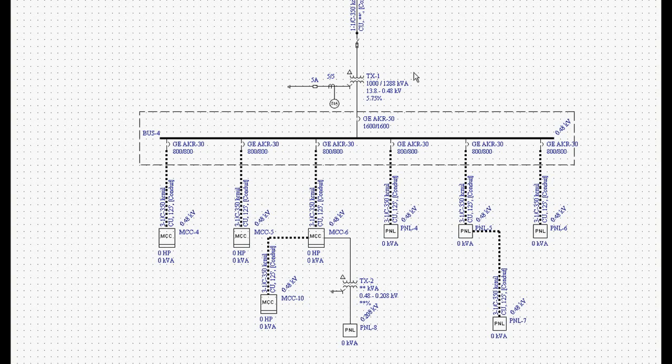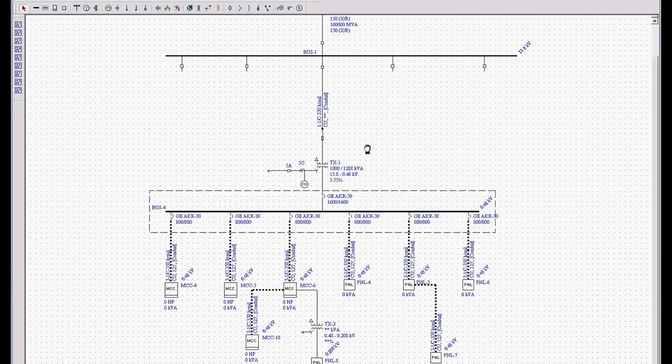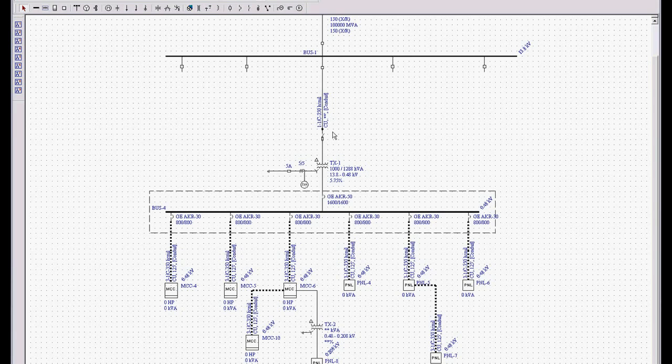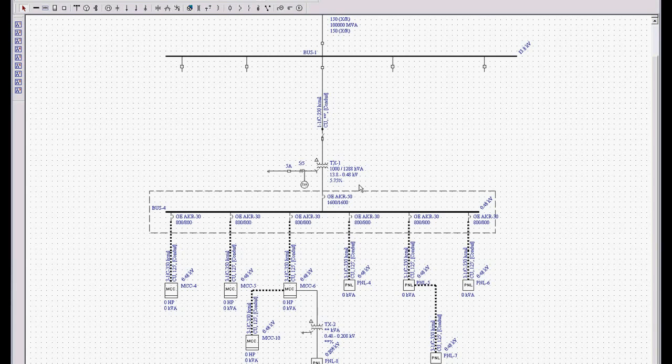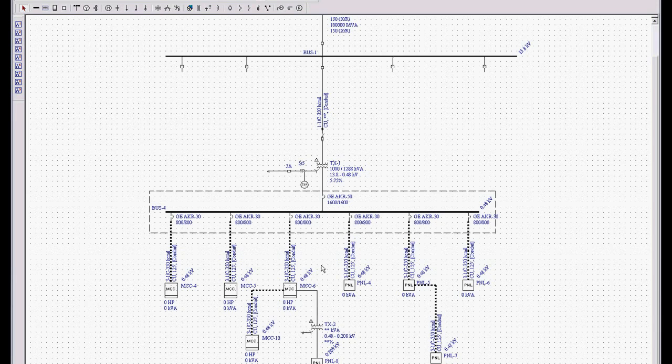Now, the goal of what you're doing when you're creating a one line diagram is create the one line, do not enter the data until you create a one line because your system is going to have multiple substations that are very similar unless it's a very small system. Take almost any system, they probably installed three General Electric or three Cutler Hammer or three square D substations that were almost identical with just minor variations.